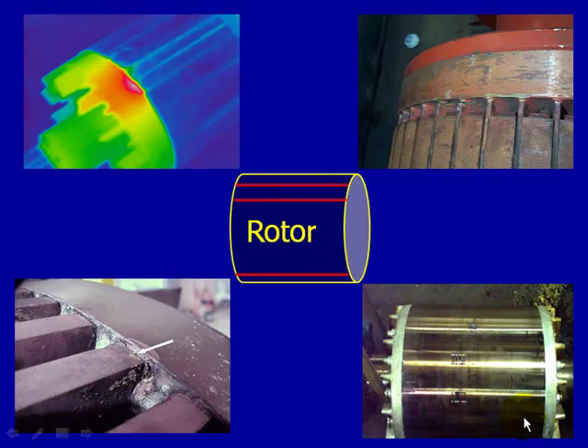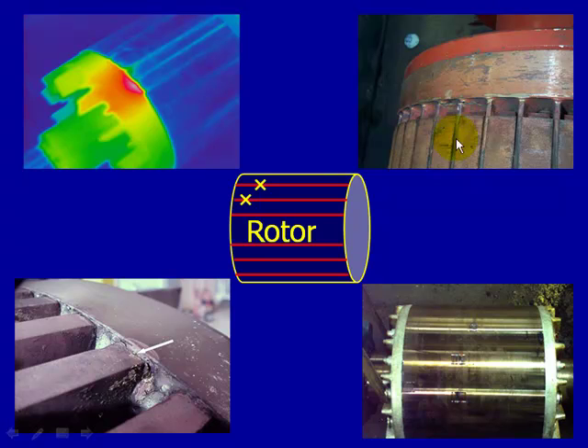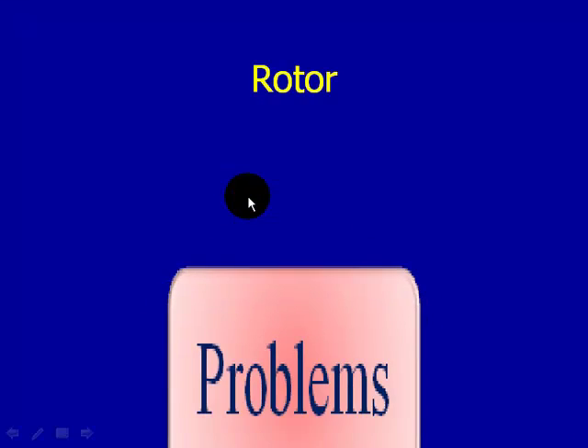As discussed in previous modules, the EPRI GE study found that essentially 10% of motor failures can be attributed to rotor bar problems. Regardless of the type of motor — open bar design or cast aluminum design — the MCE-MAX, with the MCE and E-MAX, uses comprehensive data to determine the severity of the rotor condition and trend that information over time. Our job is to alert you to the condition as it occurs and trend it as it may progressively get worse.